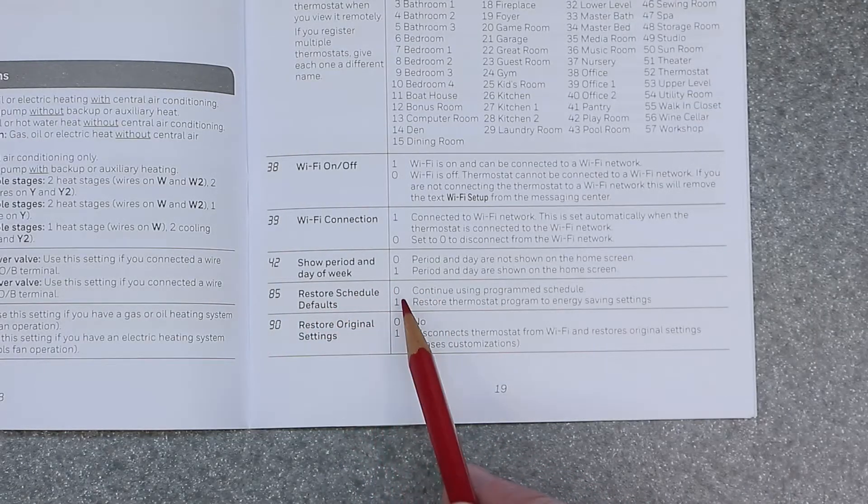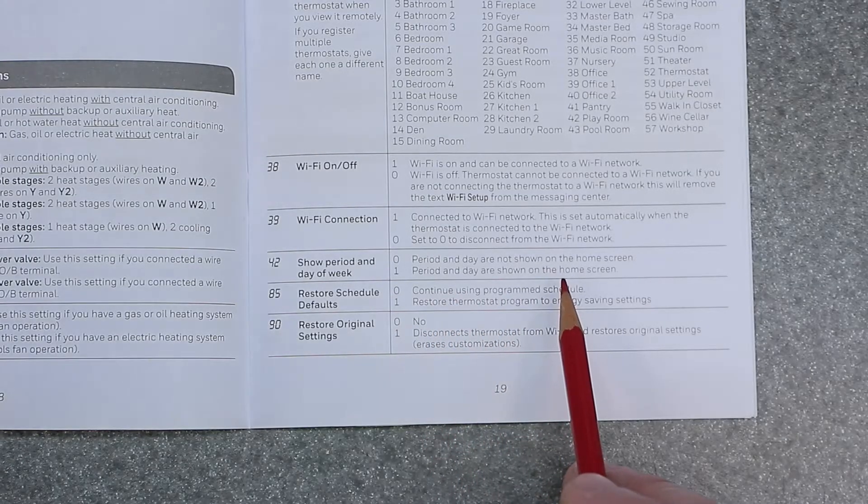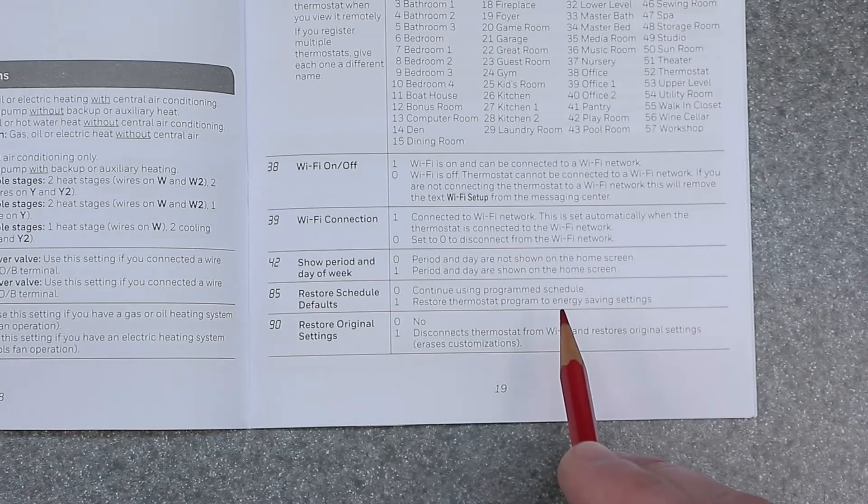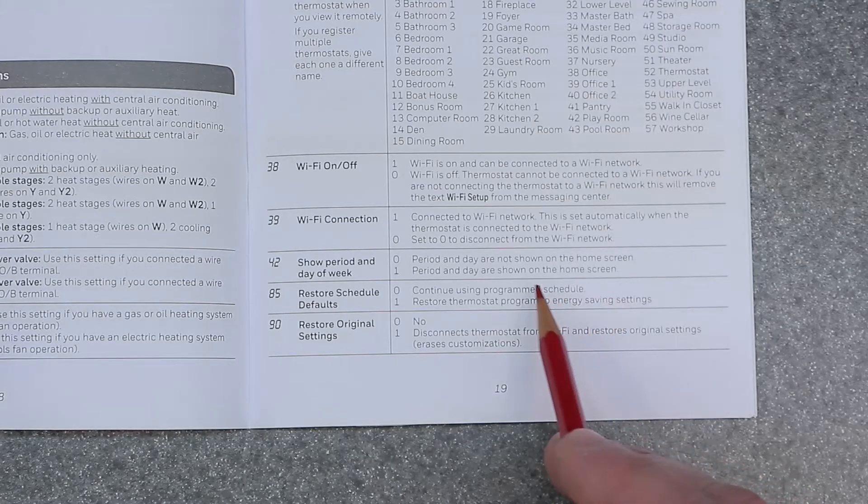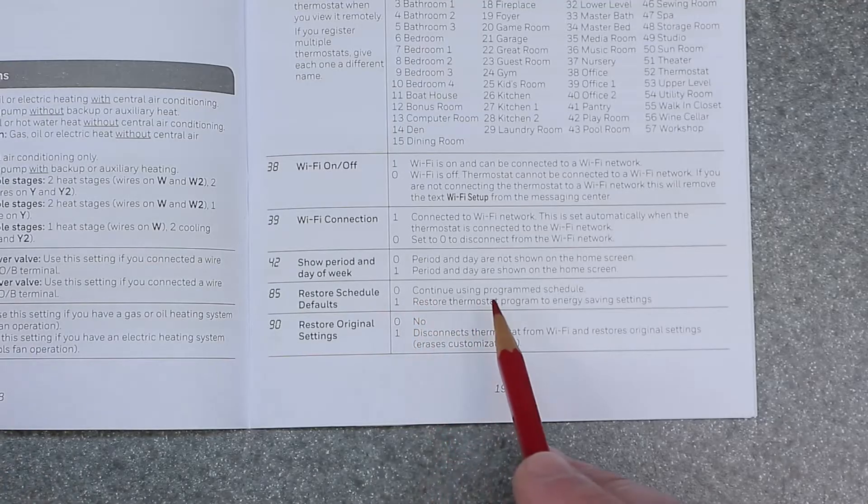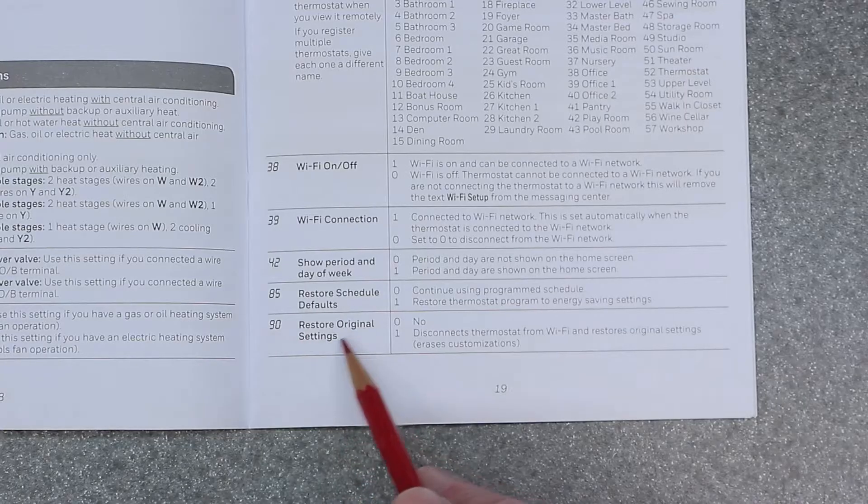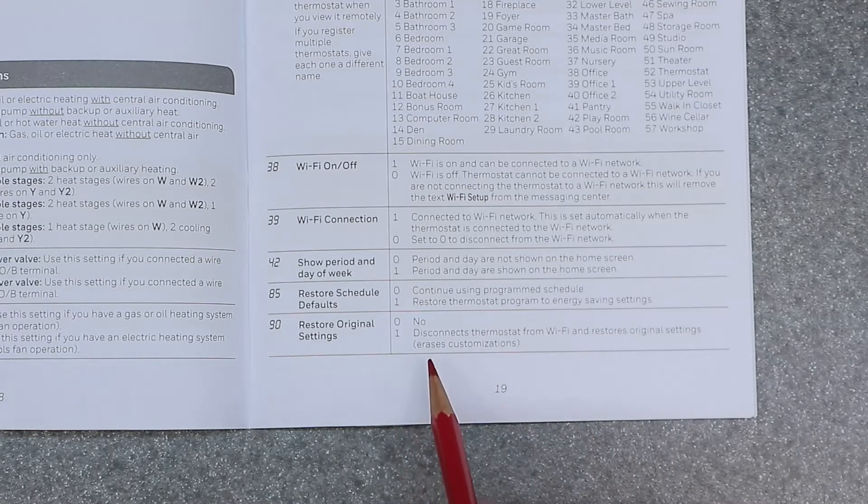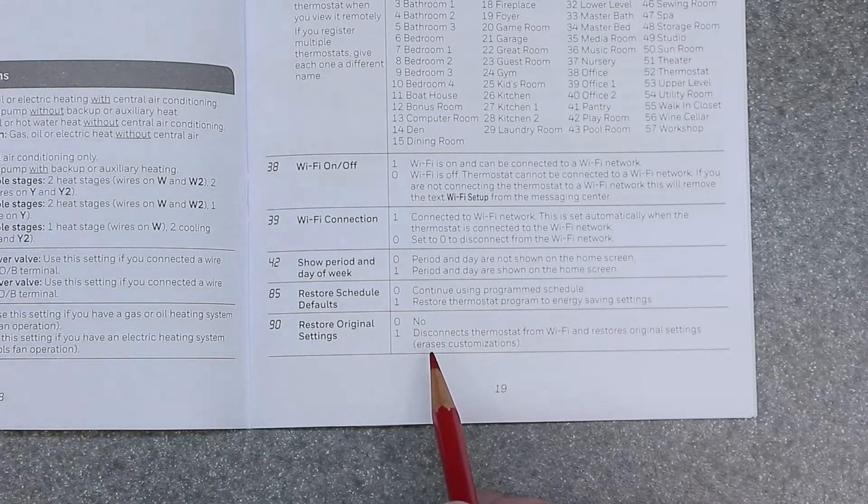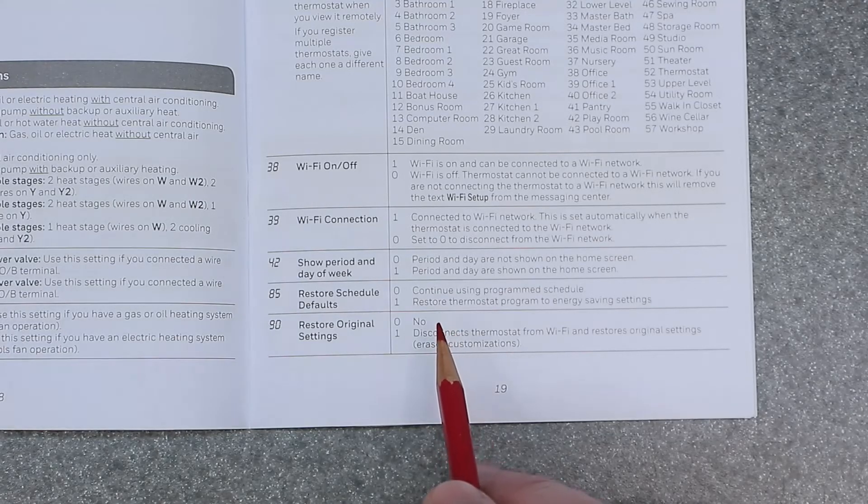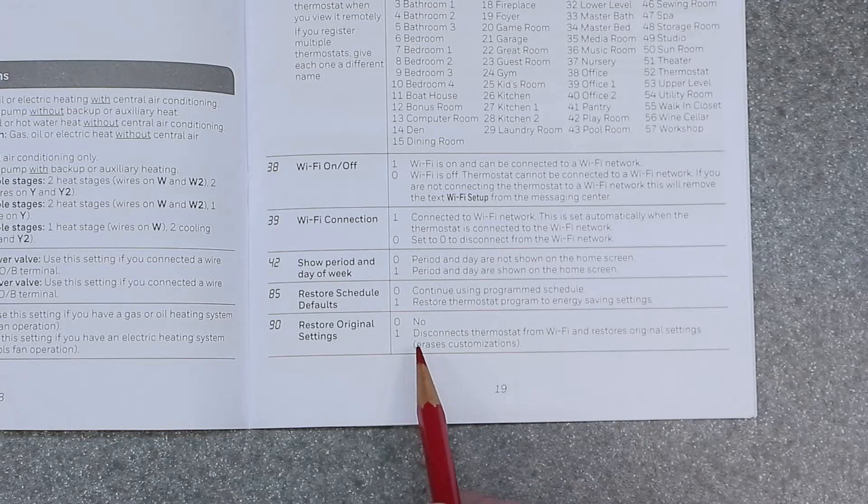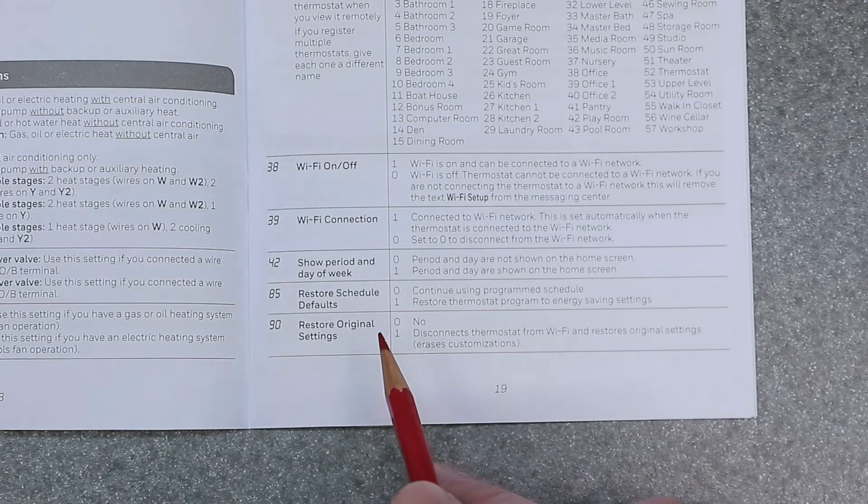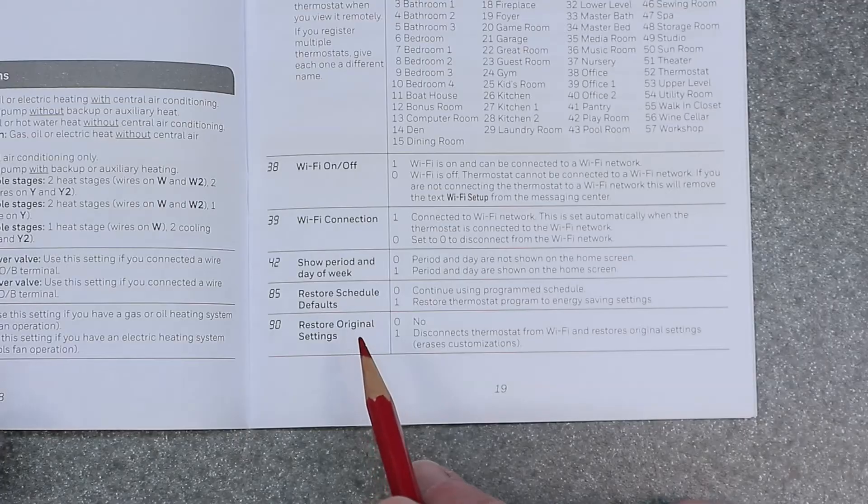85 is restore schedule defaults, which is zero continue using program schedule. So the existing schedule that you programmed, you want to keep that or one equals restore thermostat program to energy savings settings. So that's going to change it to the factory defaults. You probably don't want that because they're going to be not tailored to your liking. So I will leave that on zero and continue programming your device accordingly. 90 is going to be restore original settings. Zero equals no. One equals disconnect thermostat from Wi-Fi and restore original settings. So this right here is going to completely delete everything off the device when it comes to programming of your schedule, all your parameters. If you set up your Wi-Fi, it's going to remove all that information and you're going to have to redo that all over again. So be very careful. If you don't have to do this, don't do that and go ahead and reset your schedule only, which is 85. But if you want to start from scratch, if you bought the thing used or got it from a friend or eBay, you're going to want to do a factory restore right off the bat. And I have a separate video on how to do this.